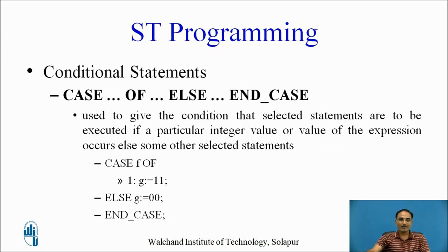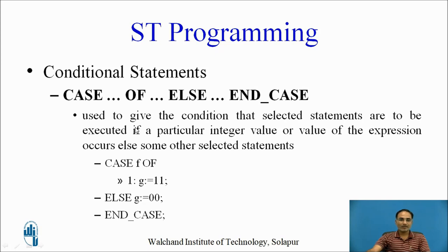The next conditional statement is CASE-OF-ELSE, which is used when selected statements are to be executed if a particular integer value or expression value occurs, otherwise some other selected statements are executed. For example: CASE F OF 1: G := 11 ELSE G := 0 END_CASE. This means if the value of F is 1 then G equals 11, otherwise G equals 0.